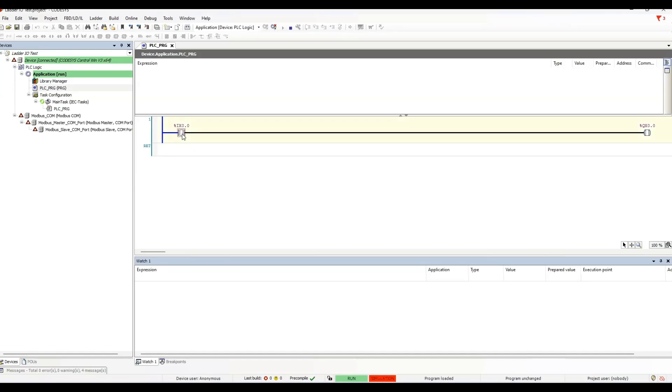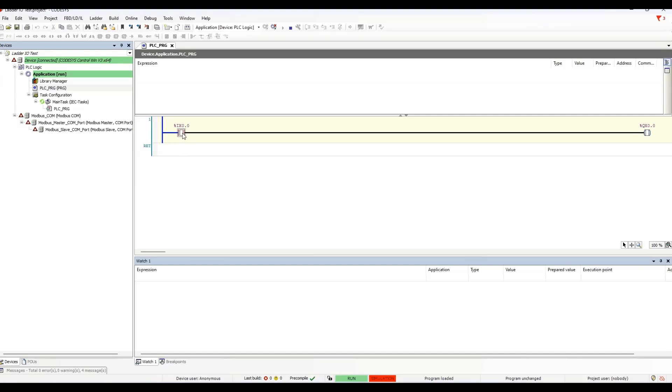Double click on the contact instruction. A blue box with the word true appears. This is now prepared to write a value of true to the simulator memory. Double click again, and a black rectangle that says false will appear. So now it's prepared to write the value of false to the assigned variable. Double click one more time, and it's back to normal. Each double click cycles through true, then false, and then back to normal.